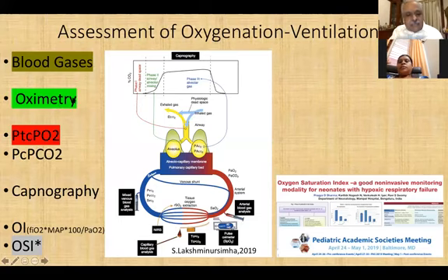the pulse oximetry. Everybody has it available. Newer pulse oximeters are now available. They are able to extract good signals from the artery. The bad signals from the venous pulsations are sometimes filtered off in the good monitors which are available with the SET technology, as we call it, or the signal extraction technology. So this is a very good thing available for us.